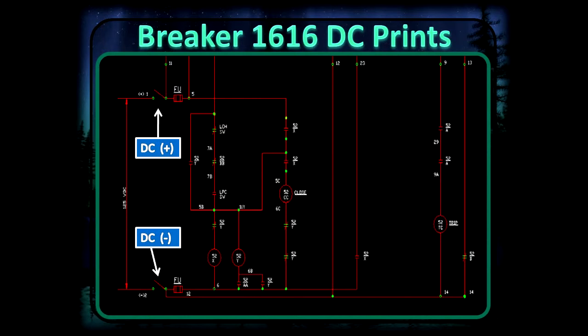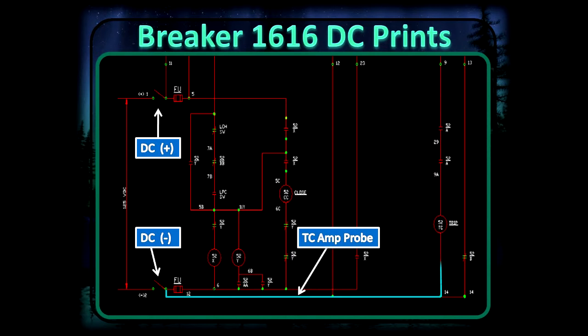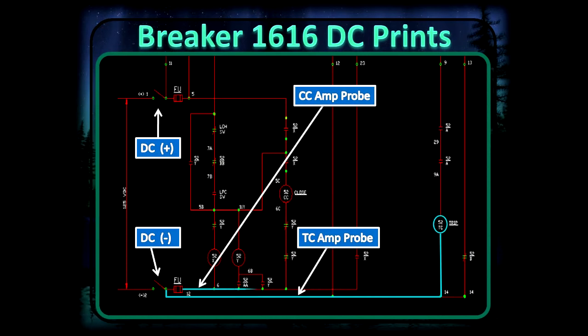We have to be able to separate your negative and your positive nodes. Next we have to find where our trip coil is, because we have to isolate that wire that goes to the trip coil so we can monitor the current that goes through it. Then, obviously, after it's open, we're going to have to monitor the close. So we have to find the close coil and isolate that wire that goes to the close coil so we can monitor the current on it as well.